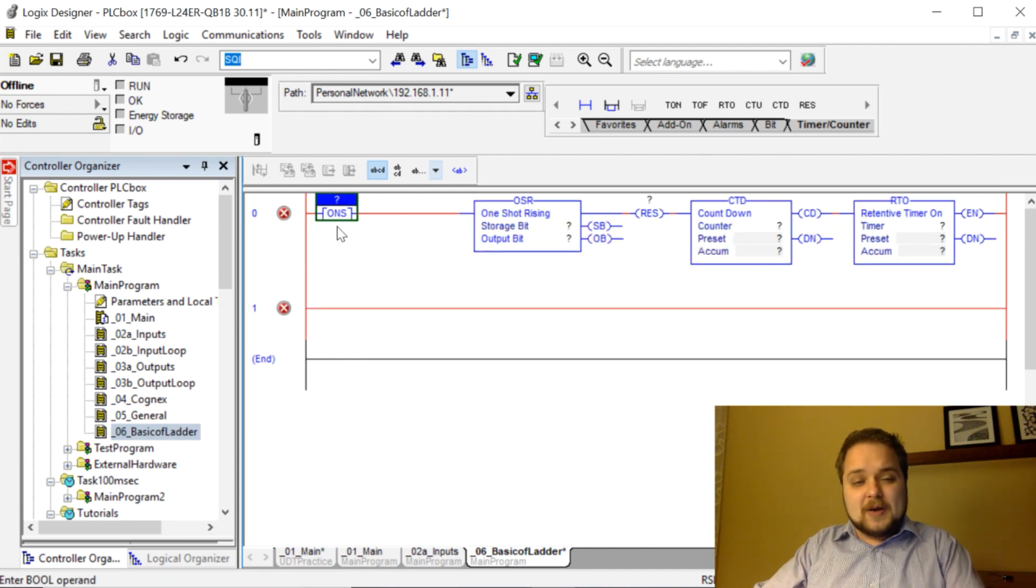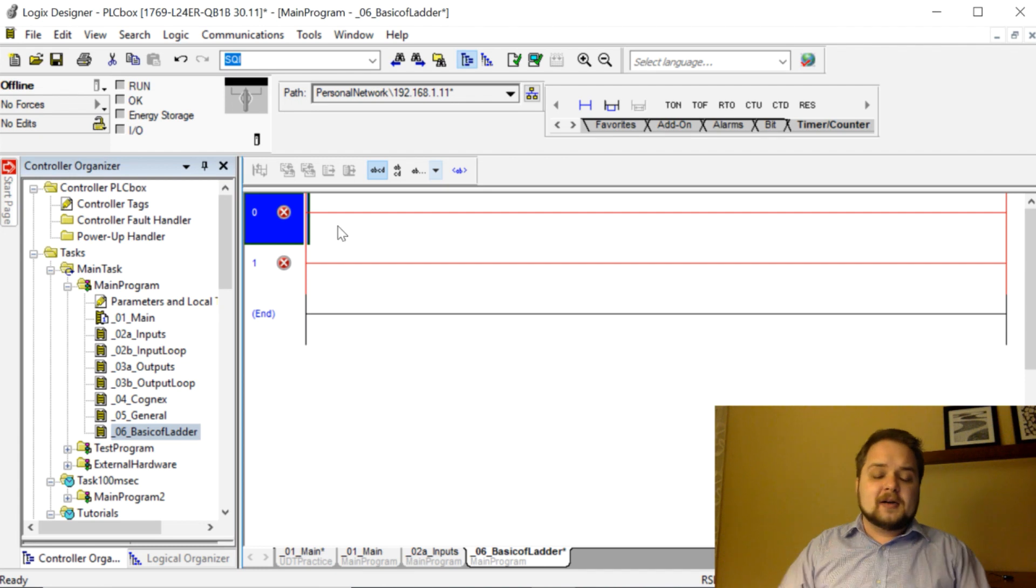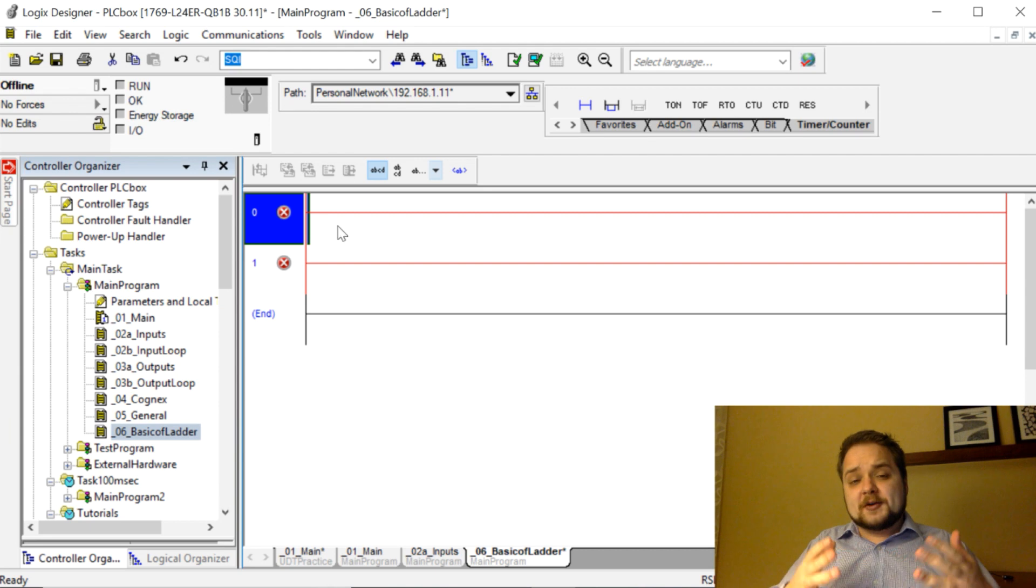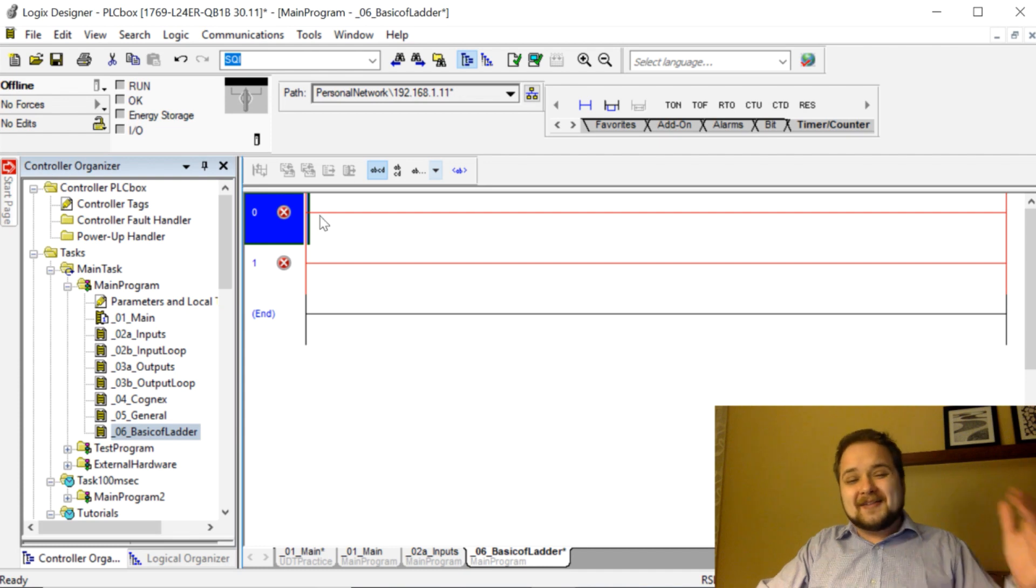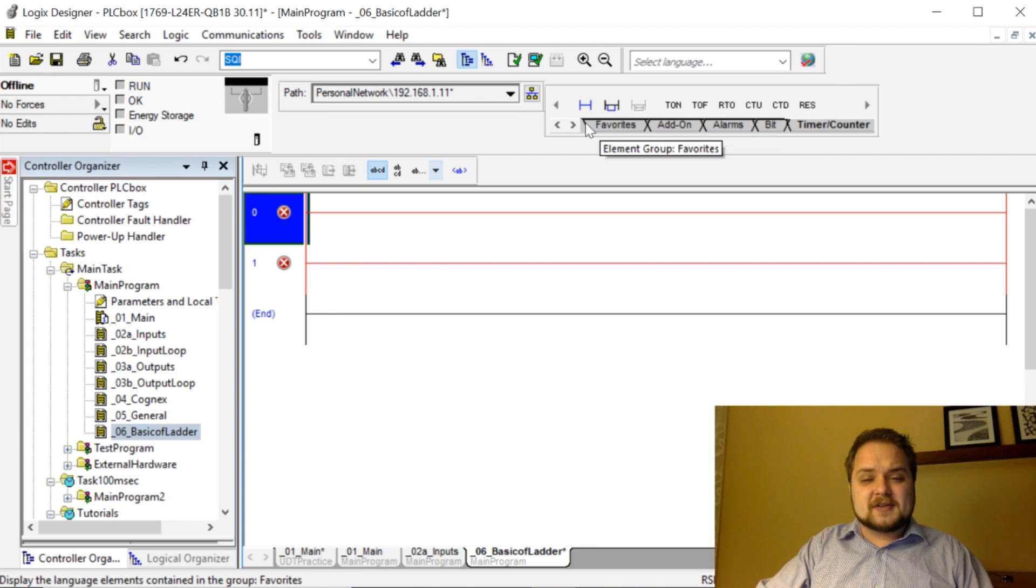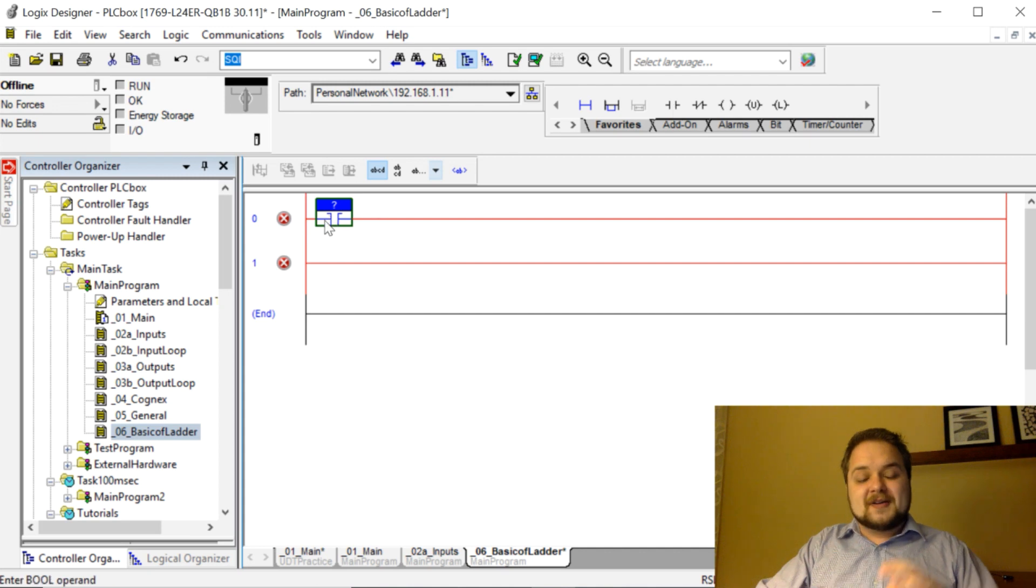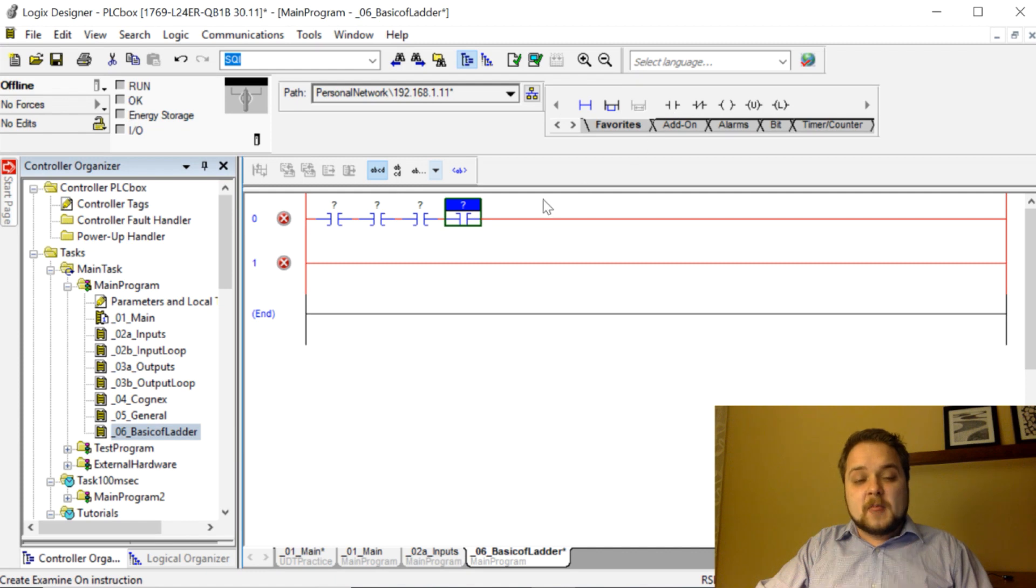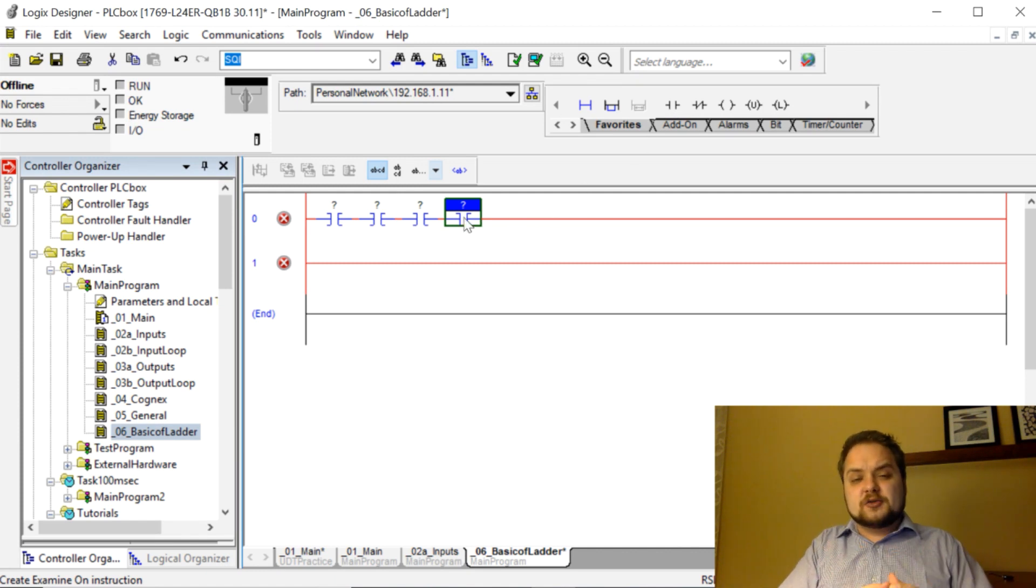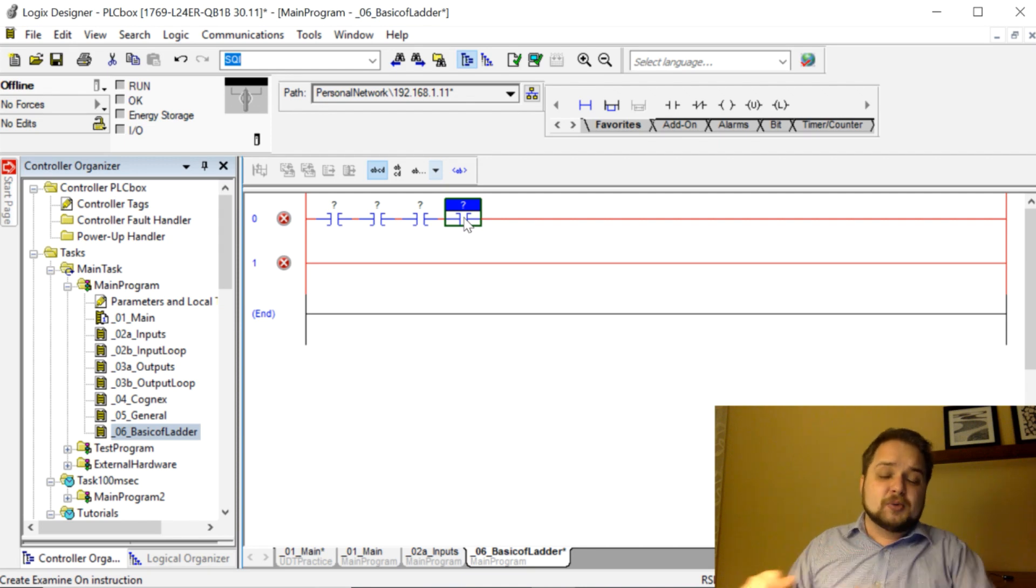What is the purpose of ladder logic? Well, ladder logic is always essentially distributed into a series of inputs or certain conditions, and then you have certain outputs or outcomes of said conditions. On the left side of your ladder, on this side you have a series of conditions. I can put five different conditions for a single output. If these conditions execute to be true, then the output is also going to execute.